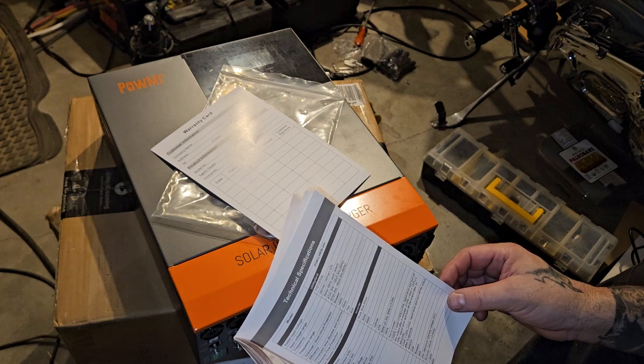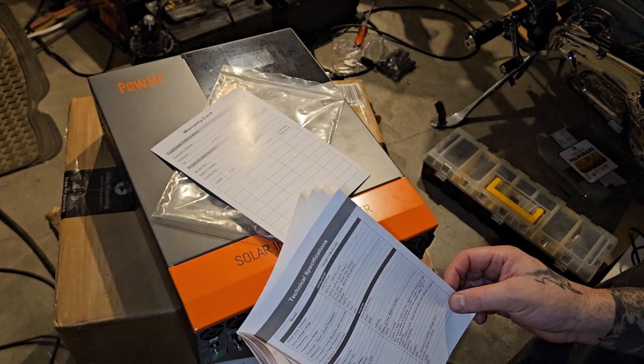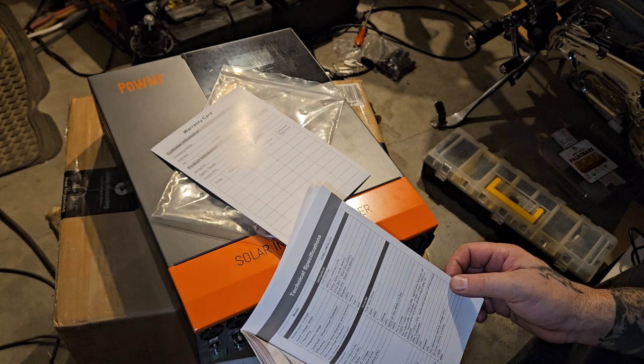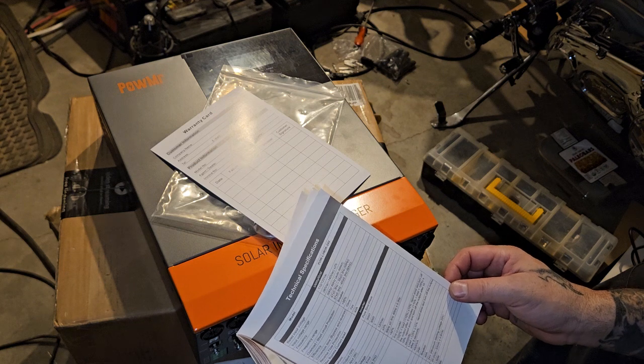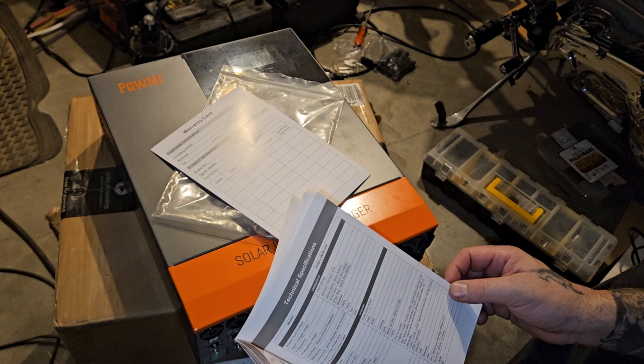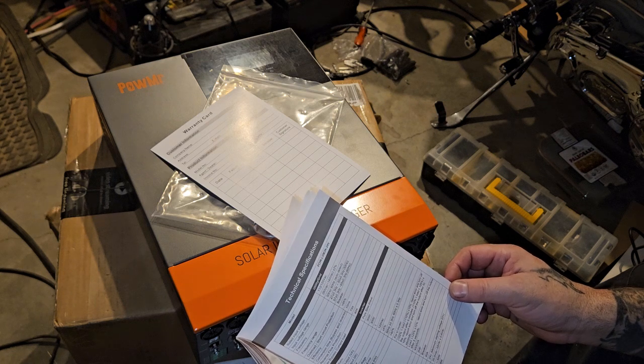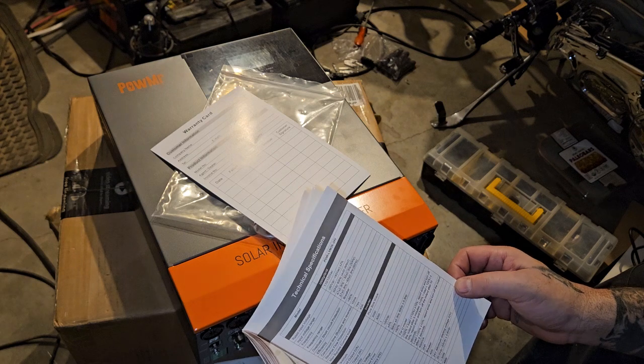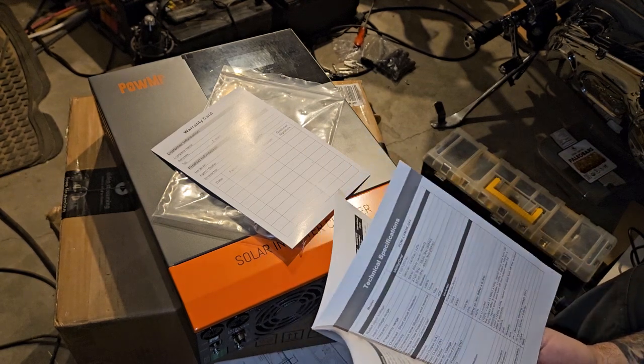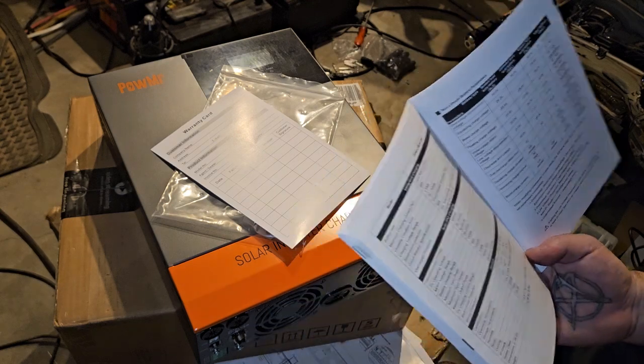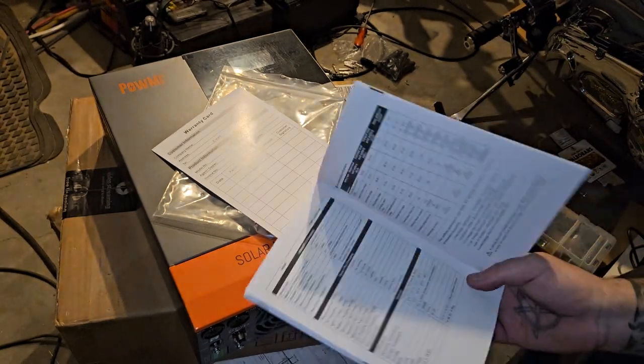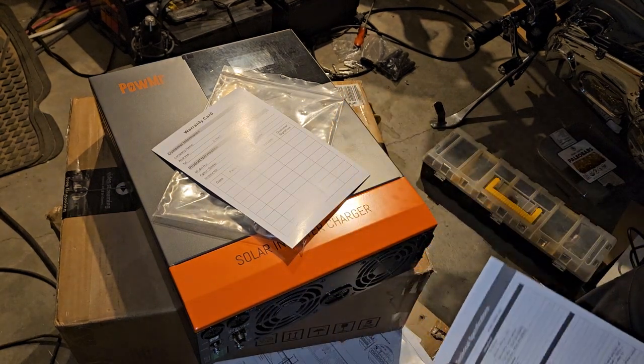So rated power 3000. Not a very big surge. Motor capability 2 horsepower. Output short circuit protection, breaker, bypass breaker 40 amps. Rated battery voltage 24 volts, minimum starting voltage 22. Power saving mode self-consumption equal to or less than 50 watts. No load self-consumption 48 watts. So it claims it'll do 3 kW, but that it will only do 1.4 kW input. So this is really kind of too many corners cut on all that.